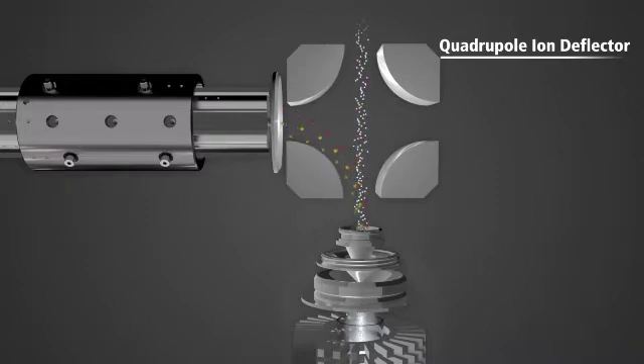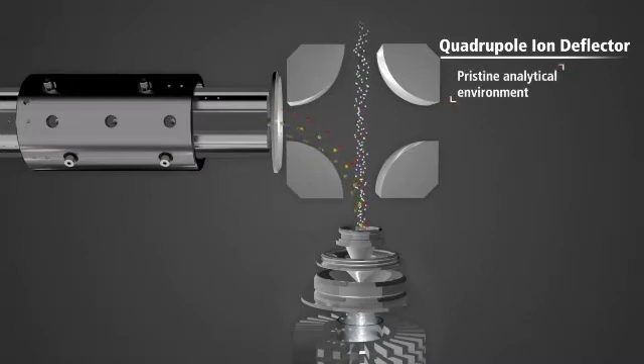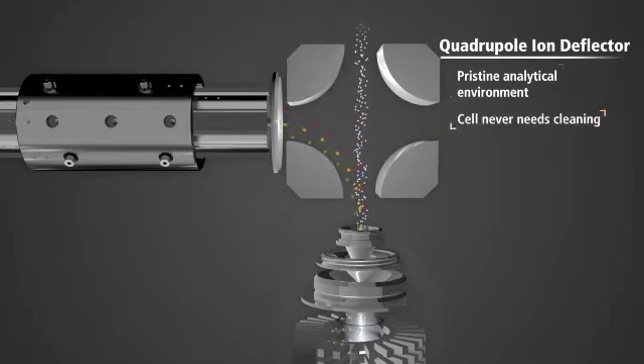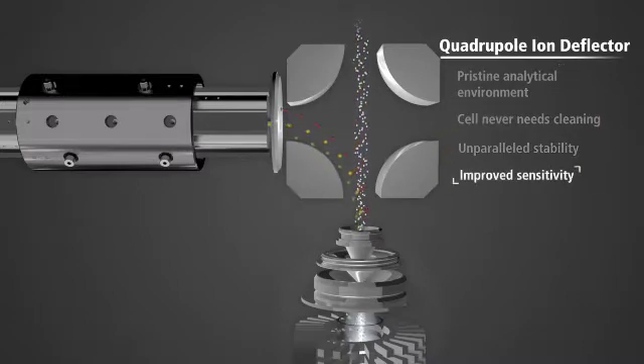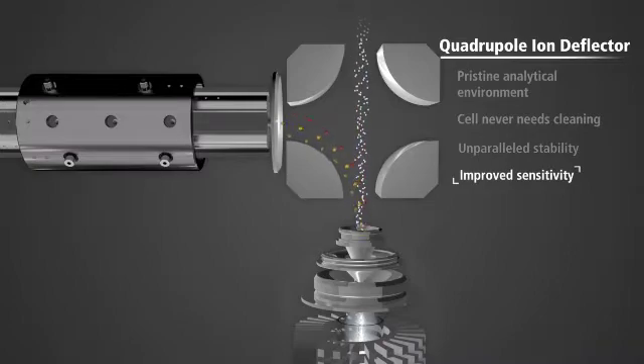In combination, the triple-cone interface and quadrupole ion deflector ensure that the greatest amount of unionized material will never reach the cell, delivering the cleanest analytical environment, the highest signal stability, most accurate results, and maximum productivity for the lab.